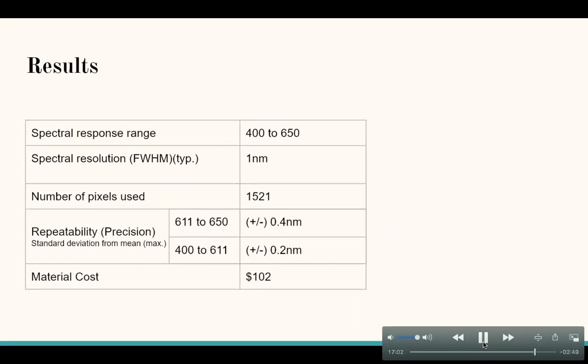When it comes to repeatability or precision of results, users can expect a maximum standard deviation of 0.4 nanometers from the mean. However, this precision improves significantly to plus or minus 0.2 nanometers for most of the spectrum between 400 and 611 nanometers. This is due to the fluorescent peaks that we used during the calibration. In the end, the entire project cost us $102.